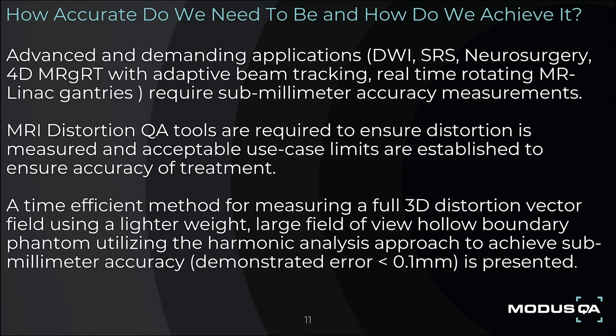How accurate do we need to be and how to achieve it? Advanced and demanding applications such as diffusion-weighted imaging, stereotactic radiosurgery, neurosurgery, and 4D MR-guided radiation therapy with adaptive beam tracking with real-time rotating MR-Linac gantries require sub-millimeter accuracy measurements. MRI distortion QA tools are required to ensure distortion is measured and acceptable use case limits are established to ensure accuracy of treatment. A time-efficient method for measuring a full 3D distortion vector field using a lightweight, large field-of-view, hollow boundary phantom utilizing the harmonic analysis approach to achieve sub-millimeter accuracy is presented.